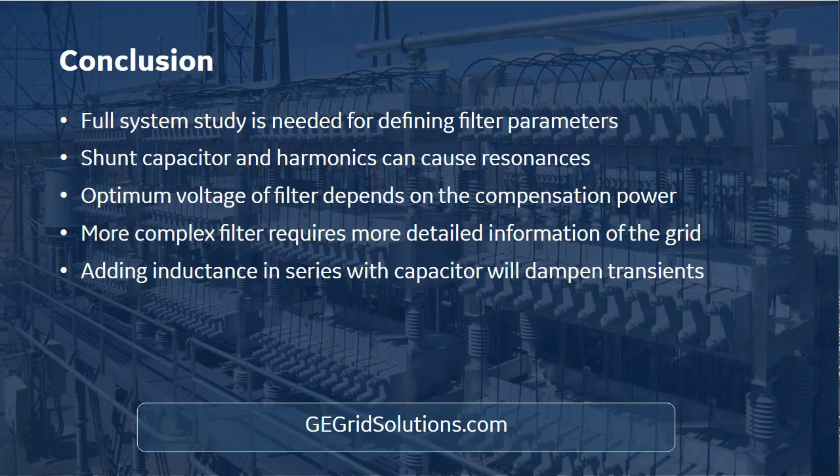Then for medium voltage, the most common place to put the filters, as I said earlier, is 1 megawatt power upwards for 33 kV, and if you have a lower power than that, then you have to use a lower voltage than 33 kV, which is, I would say, quite typical for wind farms. From inquiries that I have had, it's very typical to have this 33 kilovolt nominal voltage in there.